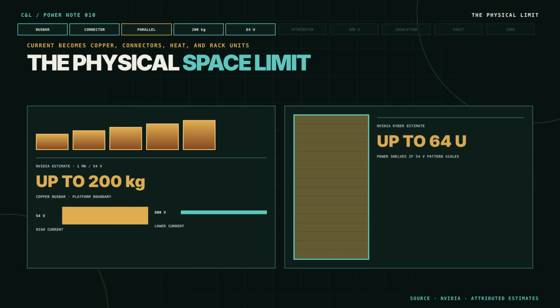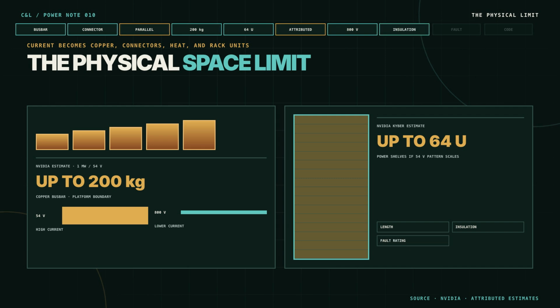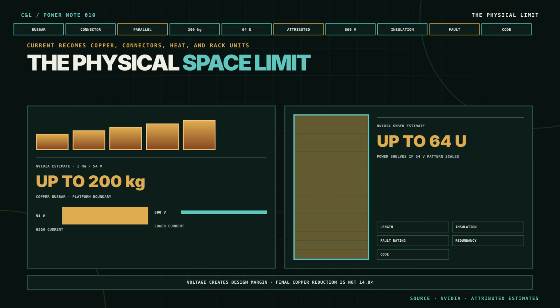Busbars must carry current without excessive voltage drop or heat. Connectors face the same current at each mating surface. Parallel conductors add routing, current sharing, cooling, and assembly complexity. 800-volt distribution cuts ideal current almost 15 times, giving designers more room to balance conductor area and loss. Final copper reduction is not 15 times. It depends on length, insulation, fault rating, redundancy, temperature rise, and code. Voltage creates margin. Engineering decides how to spend it.